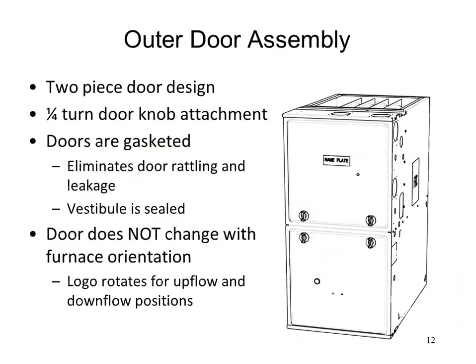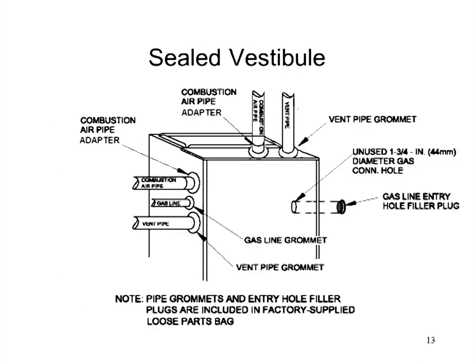If you do flip this furnace on its side, just note that the nameplate, Carrier or Bryant, will be on an angle. If you flip it upside down, however, you can pull the nameplate off and push it back on upside down, and then the nameplate will be correct in the downflow configuration. Like we said, the combustion inlet air can be on the left side, as I'm highlighting right here, on the right side or on the top, and then the exhaust vent, left side, top, or right side as well.